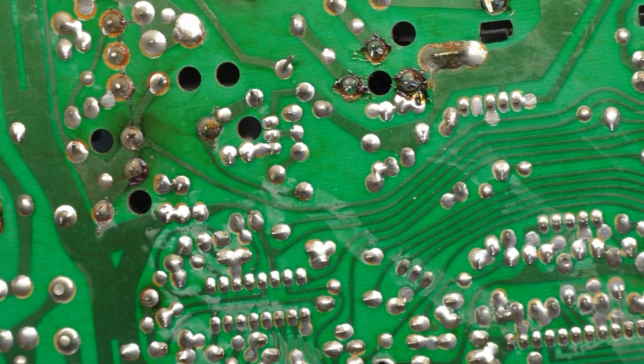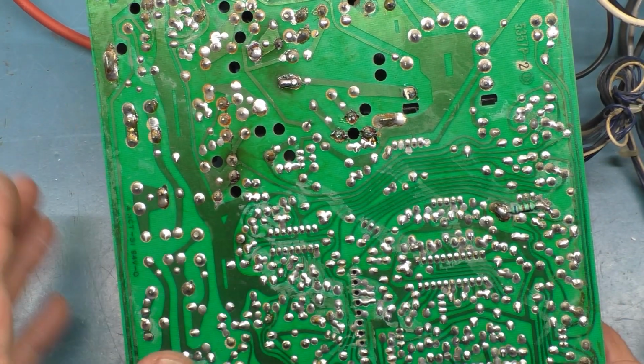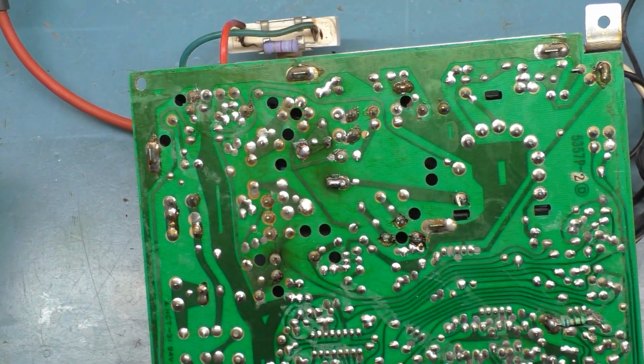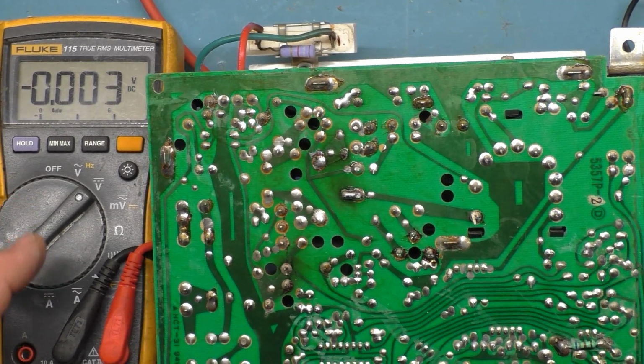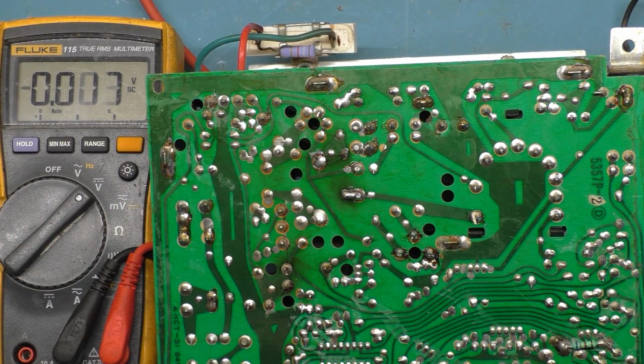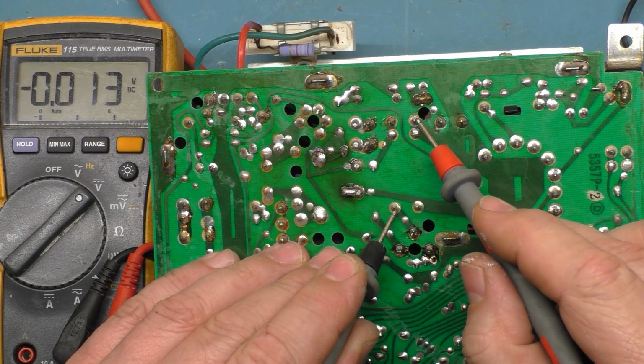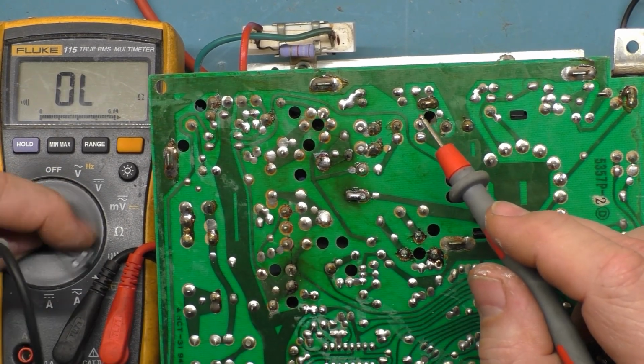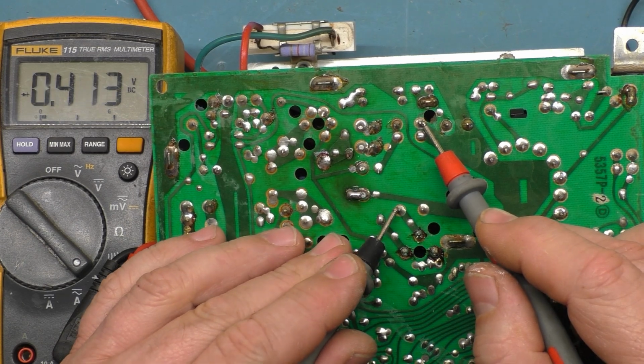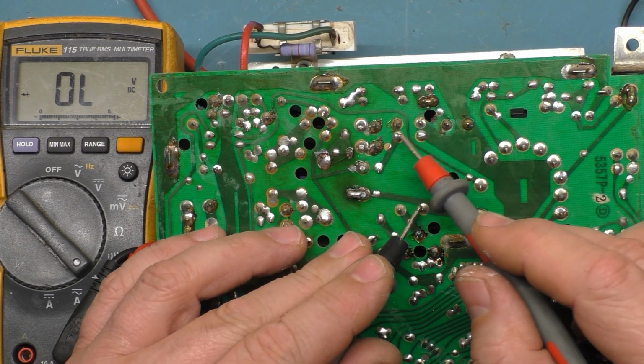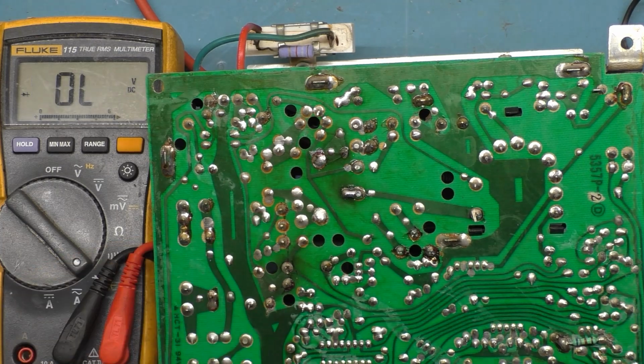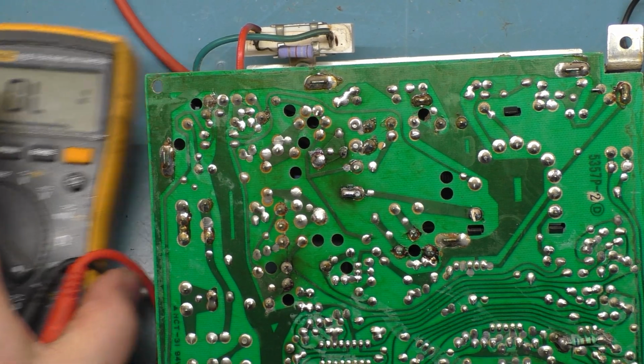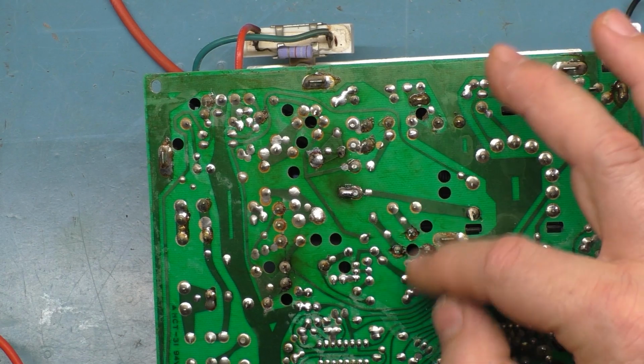Alright, so that's fine. Now, out of curiosity here, let's check that critical safety cap. Should read the same as the HOT, about .45 voltage drop, .47-ish. So if we go diagonal here, on the right setting, there you go, .48, diagonal, .48. So you're reading across the HOT when you do that. That's why this reads shorted when this reads shorted and vice versa.